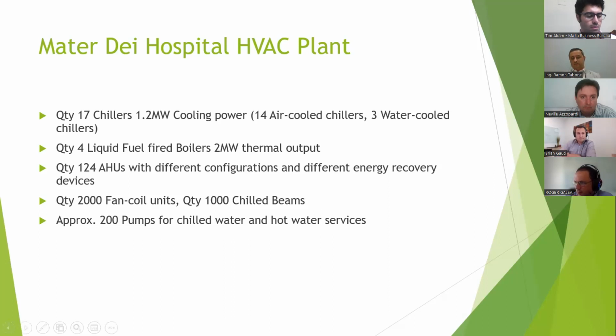The figures that I'm giving now are approximate. We have approximately 2,000 fan coil units and 1,000 chill beams, and approximately 200 pumps, which cater for chilled water and hot water services. For the non-technical, fan coil units are equivalent to air conditioning units we have at home, but instead of receiving refrigerant, they receive chilled water and hot water from the central plant. Chilled beams are similar, but they are designed to operate at a much higher temperature, we operate them above 16 degrees Celsius, so they do not condense the water from the air. And basically, chilled beams are used in the clinical areas.